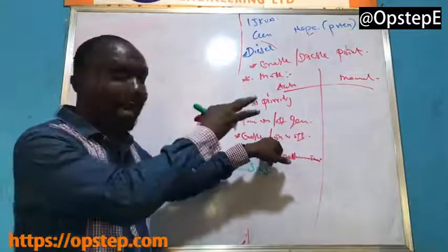The only thing it does in the auto mode is to prioritize NEPA. If NEPA is available, it puts you on NEPA, also enabling the enable line so that there's light in the house. When NEPA goes off, it turns on the generator for you, puts you on the enable, and puts the house back on generator, and then sends the text message to that effect.